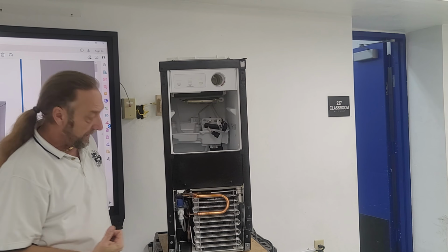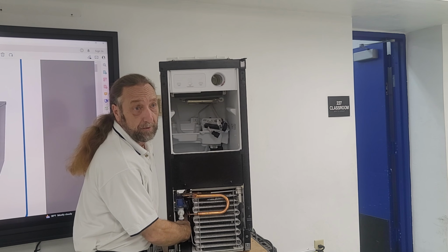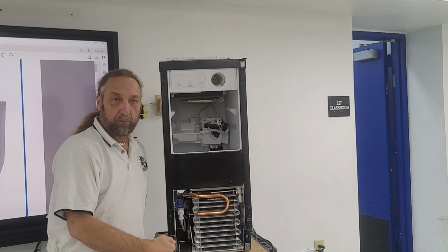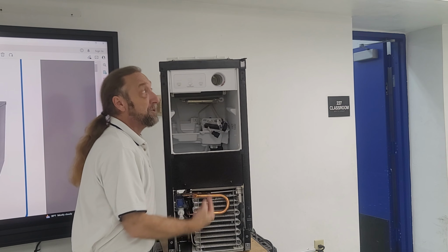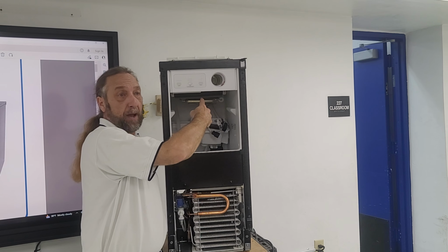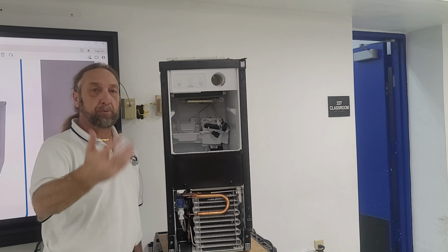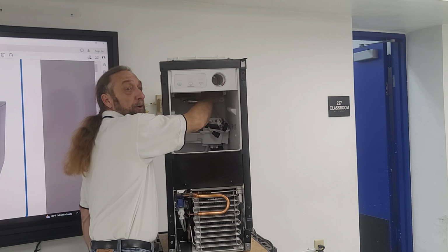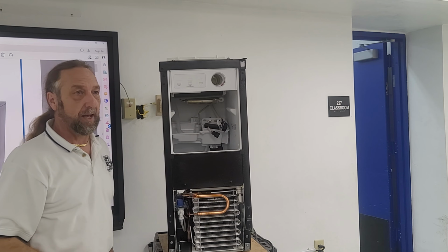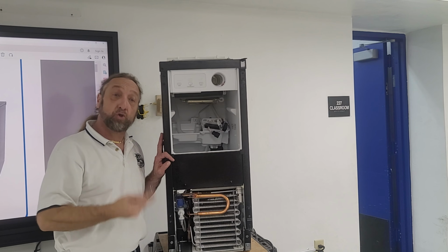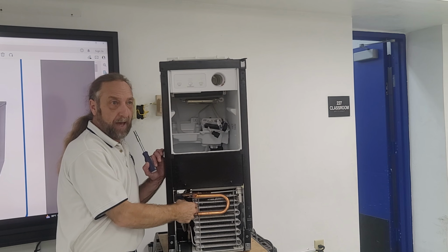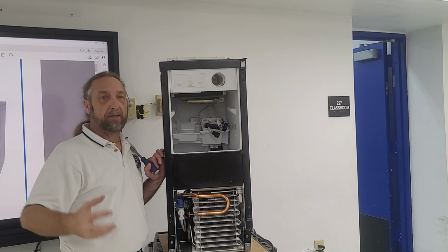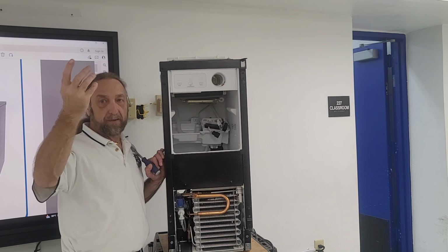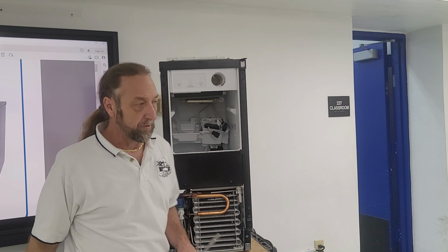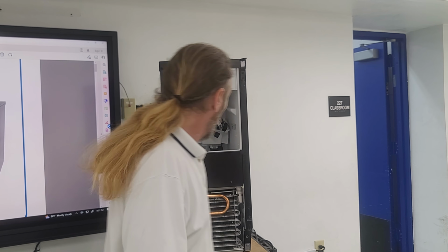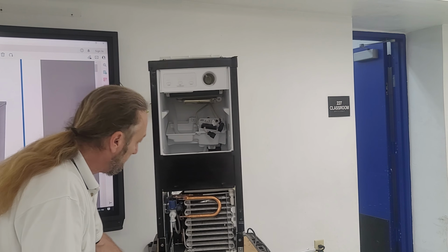We want to release the ice. The hot gas valve down here will stop the refrigerant from going to the condenser and change its direction to go straight up to the evaporator. So the compressor is pumping high pressure refrigerant into the evaporator to warm it up and cause the ice to slide off. Commercial machines do the same process. They have hot gas valves, and when they're ready to release ice, they pump high pressure refrigerant into the evaporator so that ice will come loose. So this is what we can see from the front.